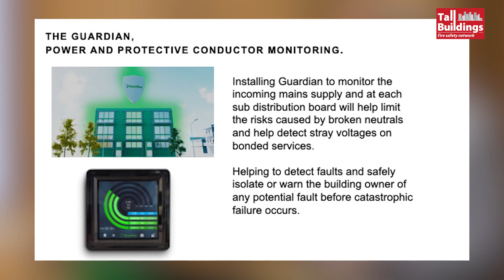So again, we go back to it. It's a power and protective conductor monitoring. Installing Guardian to monitor incoming main supply and at each sub-distribution board will help limit the risk caused by broken neutrals and help detect stray voltages on bonding services. That's exactly what it does.